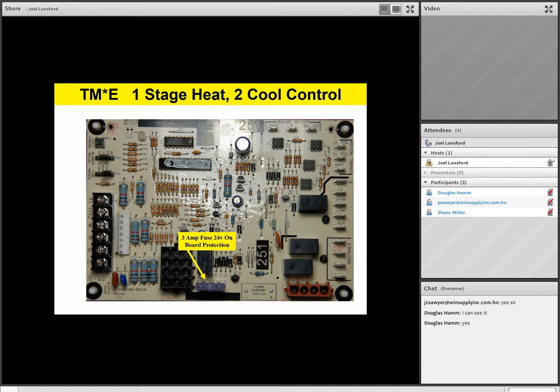Right next to the fuse, you're going to find a 12-pin harness on this board. That 12-pin harness is where all of our 24-volt inputs and outputs will be found. The gas valve, for instance, will hook into this harnessing. The pressure switches, the safety circuits, the rollout switches, and so on will all hook into that 12-pin harness.